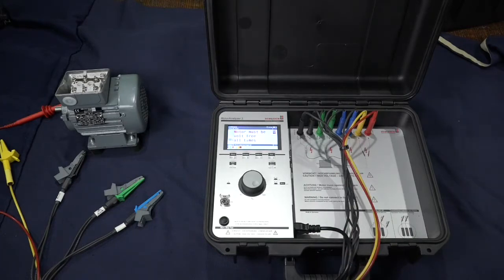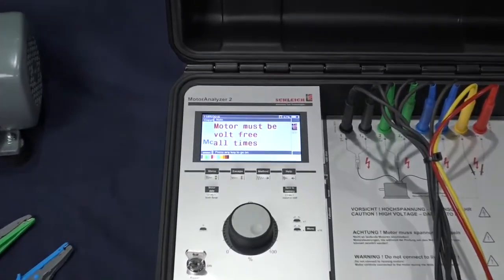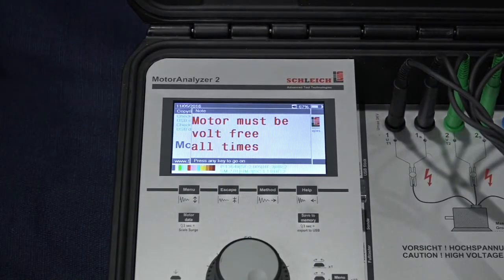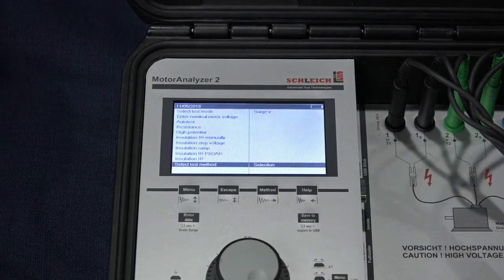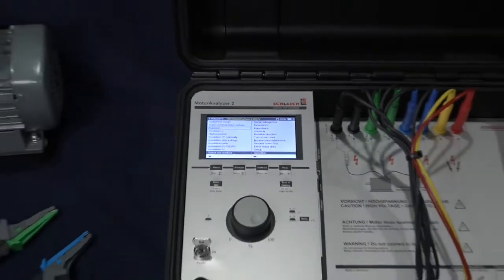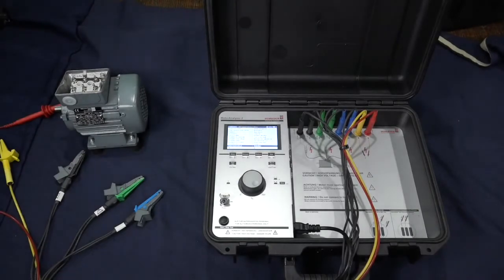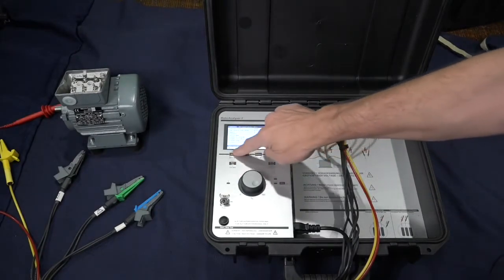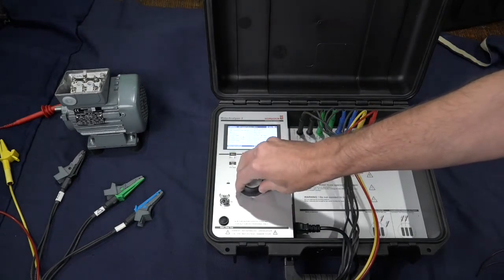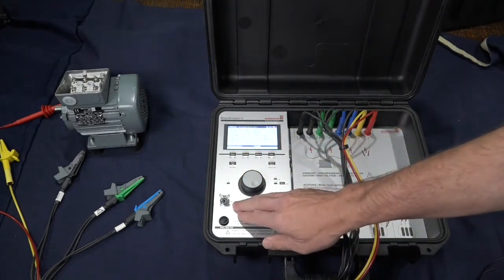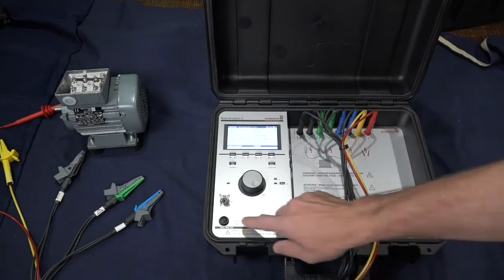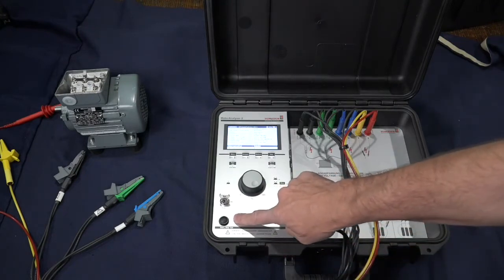You can see there's a message on the screen when it boots up asking us to make sure that we're connecting a motor that is not energized. If we did, we'd have quite a mess. Backing up, looking at the available controls and the test leads. Here we have our display, obviously. We have a set of soft keys here, a whiz wheel for entering and selecting options, the on-off switch, key switch, and then the test button that you see down over here in the left-hand corner.